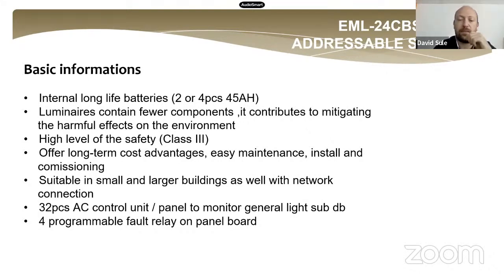It's an 8-digit ID. So when you install the light, you just need to write down this unique ID into the drawing. And during the commissioning, the panel will collect these addresses from the lights, and it's very fast. Because it's a DC 24 volt system, the panel can read all of the 120 luminaires in a maximum of 30 seconds.